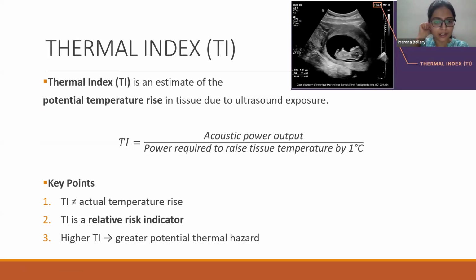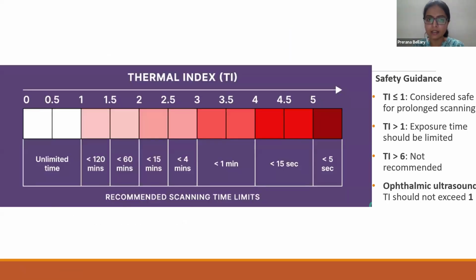It is the power required to raise the tissue temperature by 1 degree Celsius. So it is not the actual temperature rise, it is a relative risk indicator. A higher TI would mean a greater potential thermal hazard. Right? So thermal index ranges from 0 to 5. The FDA has approved certain guidelines where a thermal index of less than or equal to 1 is considered safe for prolonged scanning. If it is more than 1, then the exposure time should be limited and definitely should not be more than 6. But when we are doing ophthalmic ultrasound, it should not exceed 1.